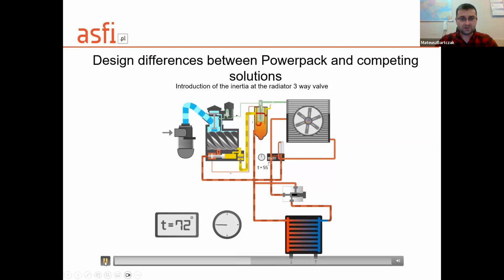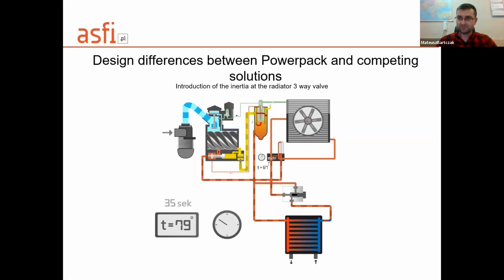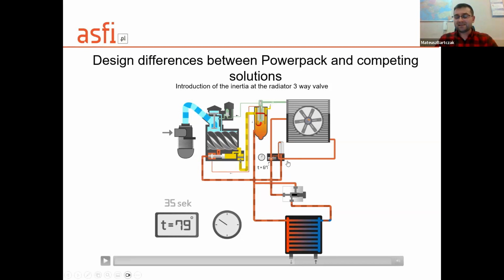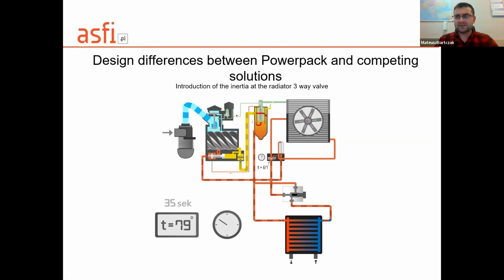So after 35 seconds, okay, pause. After 35 seconds, this valve can see this increasing temperature of oil. The stroke time is a parameter of the valve. It tells us how much time this valve needs to make a full move from full open to full close, or from full close to full open. Usually this valve in a compressor has a stroke time of 20 seconds.